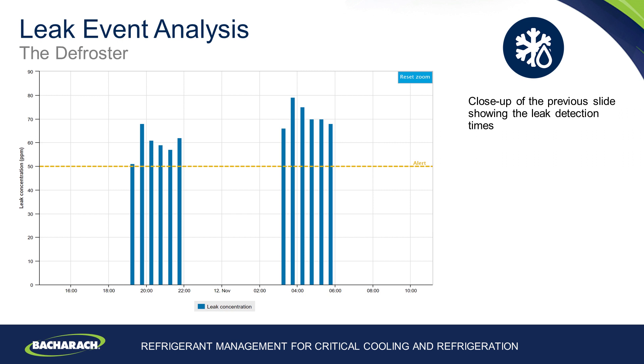If an engineer attended outside the defrost period looking for a leak, they may not detect it with a handheld gas detector. Here we see the defrosting event in more detail over a shorter time period — you can see the leak occur for a two-hour period while the system is on the defrost cycle, and once the refrigeration effect is back and the system is in cooling mode, the leak disappears. The PPM values are very low indeed, indicating a very small leak, making early leak detection imperative to good system performance.